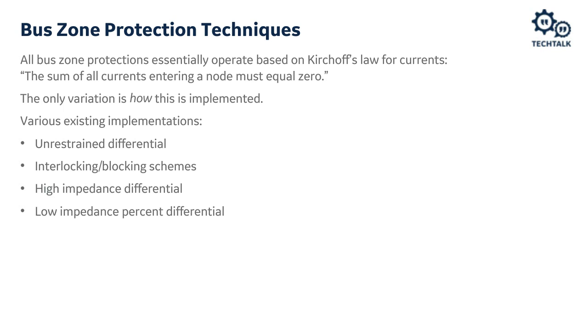We use the differential principle for bus protection, based on Kirchhoff's current law: the sum of all currents entering a node must equal zero, or current-in equals current-out. The various implementations are: the unrestrained differential, the interlocking or blocking scheme, the high impedance differential, and the low impedance percent differential. Our focus today will be on the low impedance protection, with brief coverage of the others.